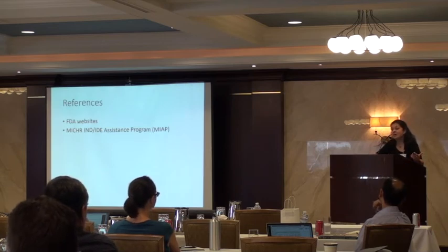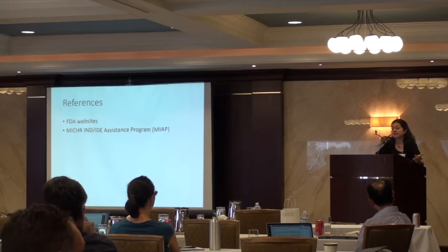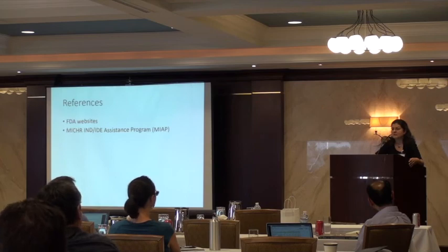The second one was a novel device, where we wanted to make sure we were using the right pathway, and that the trial we were designing was going to allow that device to get the appropriate clearance or approval. There, the in-person meeting was great, and they really looked at our design and talked through with us what it will and will not achieve within the drug device branch. So I hope those examples help.